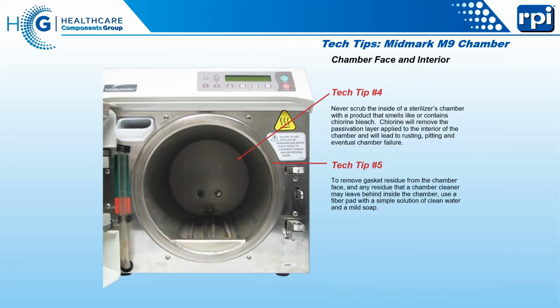Okay, never scrub the inside of a sterilizer's chamber with a product that smells like or contains chlorine, end of story. If your customer complains that the door gaskets are pulling out or falling out, 9 times out of 10, they've got some goop on this surface. So get a Scotch-Brite pad, a little bit of water, a little bit of stainless steel cleaner if you need it, polish that off of there, and more times than not, the gasket will stop falling out.